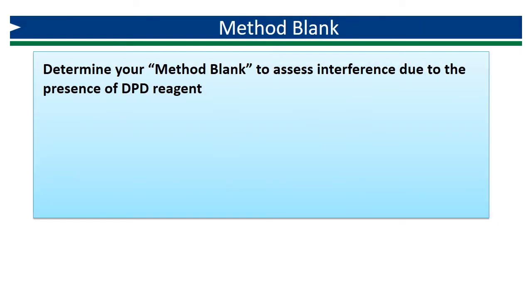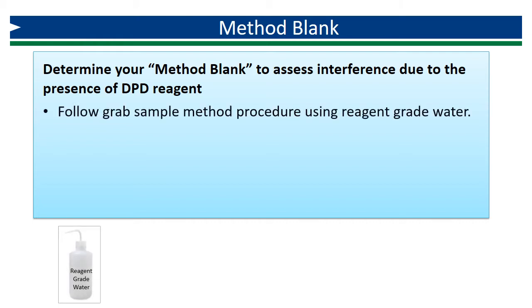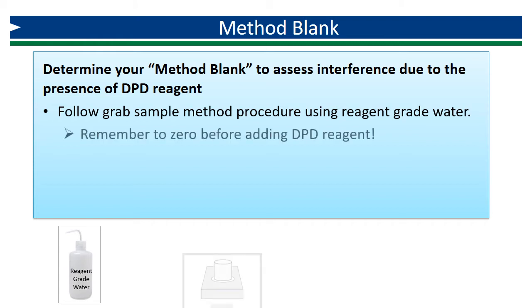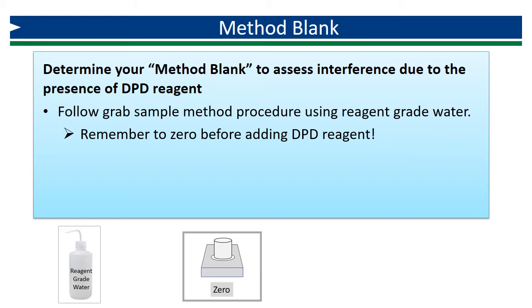The first step is to determine the method blank value for the lot of reagent you are using in order to assess the level of interference caused by the DPD. The procedure for determining a method blank involves following the procedure for the chosen method, with the exception of the sample matrix — rather than using water that may or may not contain chlorine, use reagent-grade water that does not contain chlorine. Remember to zero before adding DPD reagent.